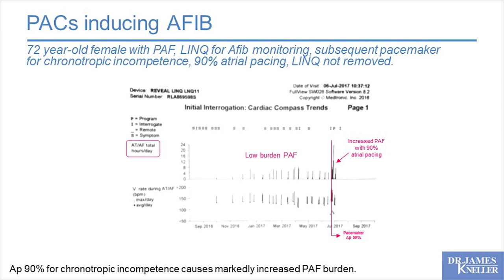As a demonstration, this figure shows a patient implanted with a loop recorder, the Medtronic Reveal LINQ, for AFib monitoring. A low burden of PAF was discovered with overall chronotropic incompetency. A dual-chamber pacemaker was implanted with 90% atrial pacing. The loop recorder was not removed and demonstrated a marked increase in AFib burden following pacemaker implantation. This was attributed to the PAC-like effect of atrial pacing. This result demonstrates how AFib initiation can be a substrate phenomenon, originating from the atrial chambers without any contribution from pulmonary veins.